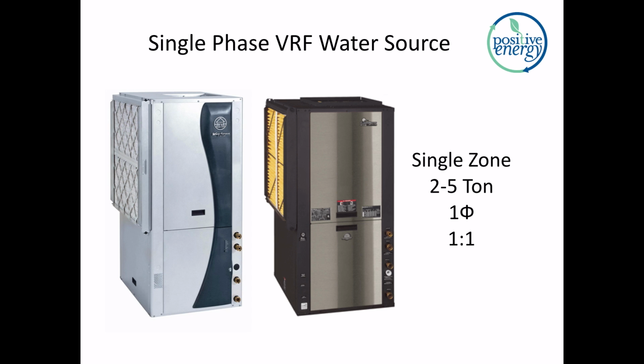These are very forward-looking systems. They are still limited to that one-to-one mode. So in a big house, you're running a big system and you are reliant on airside zoning, which could be said to be somewhat defeating a little bit of the potency of the VRF product. But there are single-phase, one-to-one VRF water source heat pump systems out there. Talk to me more about this before you jump into one of those. There's a lot more to say here. We need to keep moving.